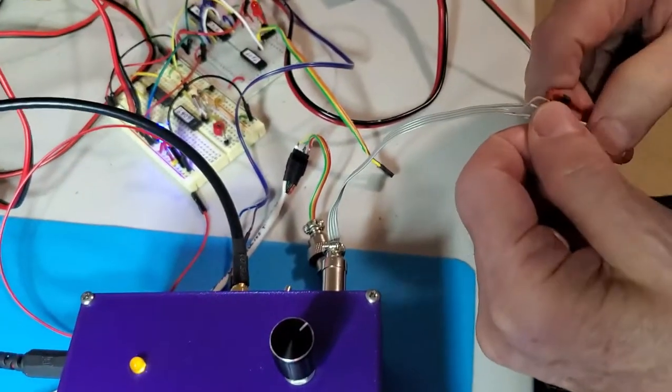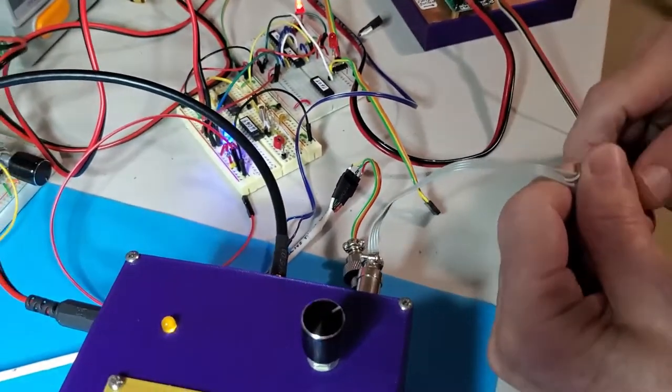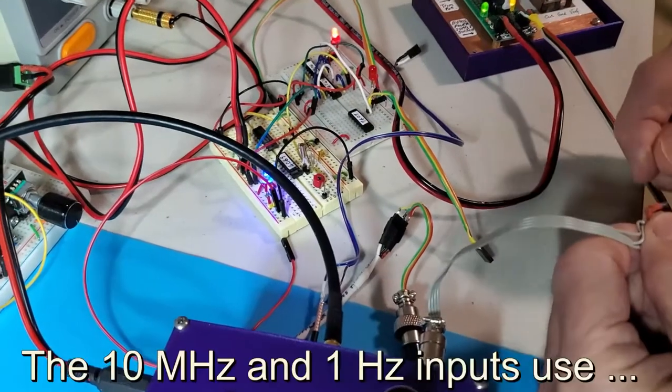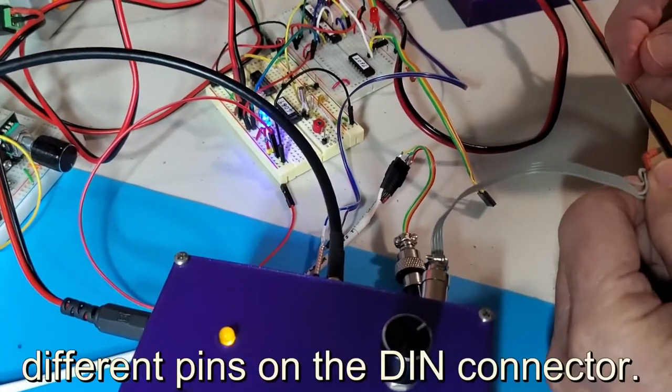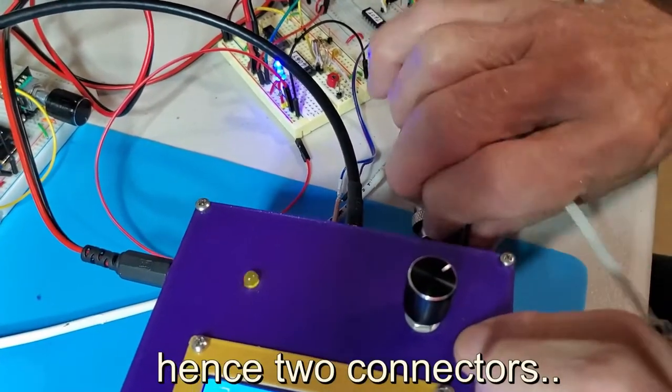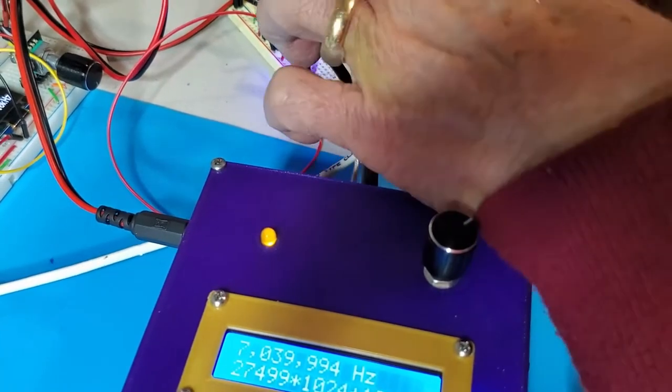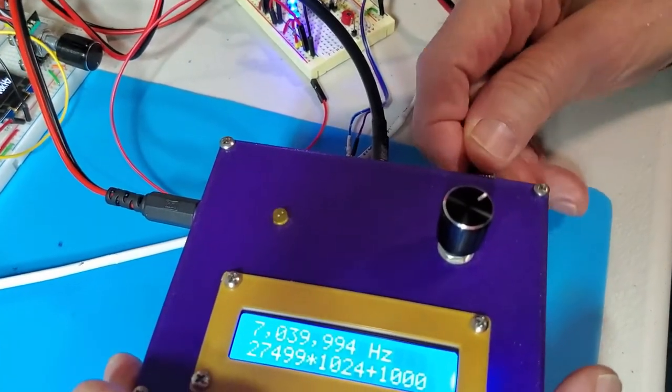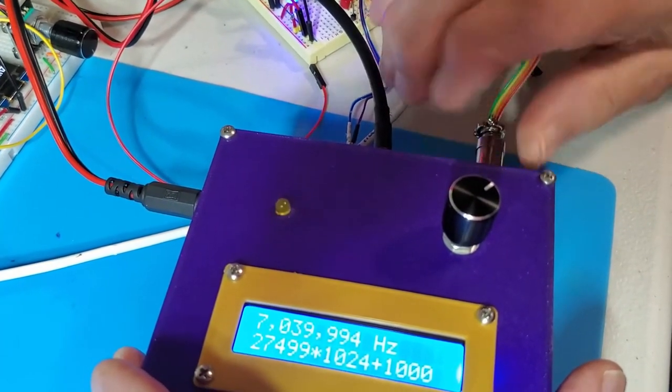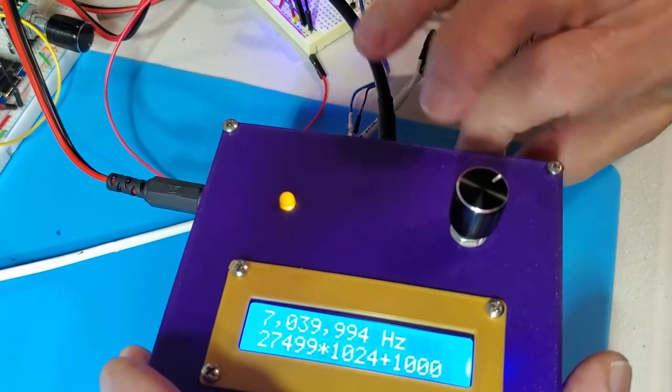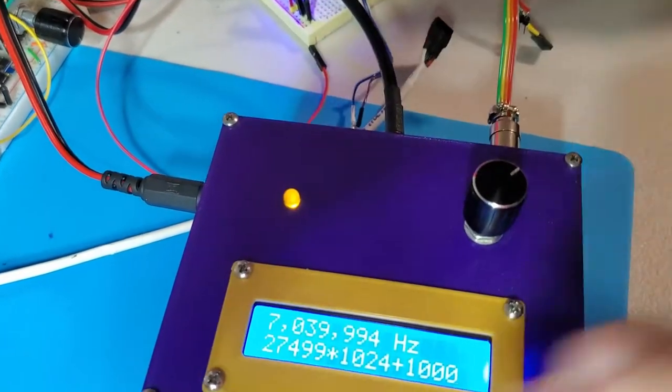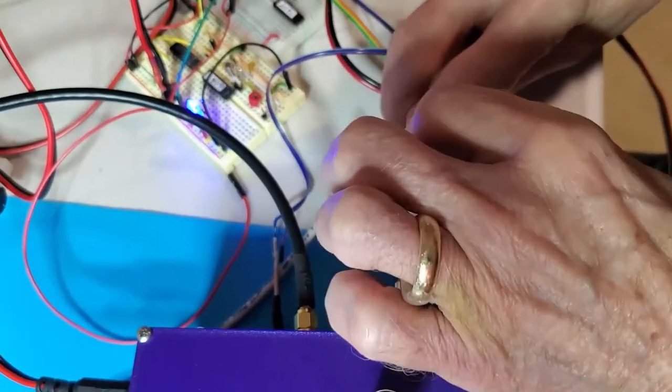Now I'm going to unplug the OCXO. This is the wrong connector. Let me take this off. Unplug the GPS here. Plug this connector in. Because we're going to be doing one second, not 10 megahertz. And flip this to the one second position. And we will plug this time base in here.